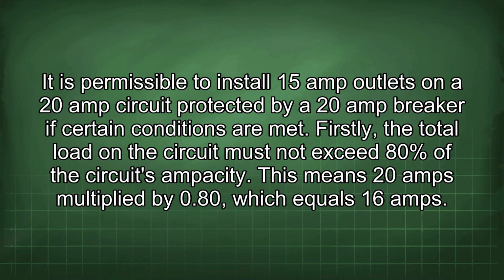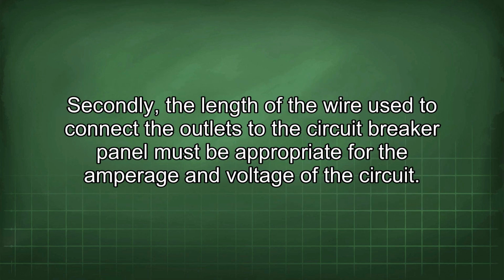It is permissible to install 15 amp outlets on a 20 amp circuit protected by a 20 amp breaker if certain conditions are met. Firstly, the total load in the circuit must not exceed 80% of the circuit's ampacity. This means 20 amps multiplied by 0.80, which equals 16 amps. Secondly, the length of the wire used to connect the outlets to the circuit breaker panel must be appropriate for the amperage and voltage of the circuit.